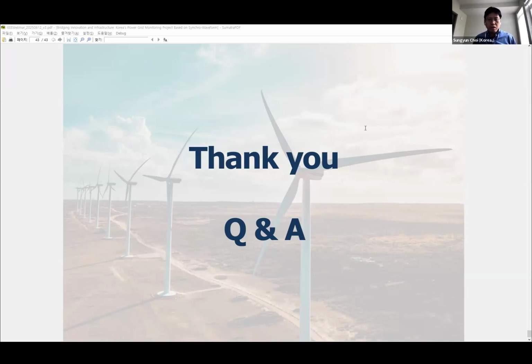Thank you, good questions. Actually, many monitoring systems provide automatic protection, in other words RAS, remedial action schemes. When a fault happens, it automatically takes actions in a few milliseconds to prevent transient instability or angle stability issues. It should be very fast, because if it's too late, the system collapses, so this kind of alarm should pass quickly.